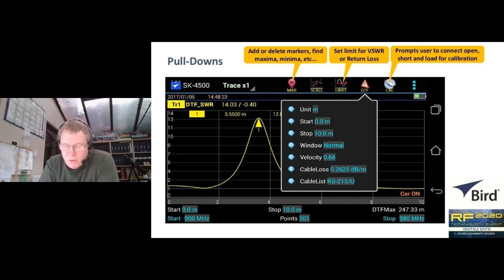This next image shows an example of one of the pull-down menus. This is the menu in which we can specify the type of cable, from which the tester can derive the velocity ratio and hence the speed of propagation through that cable. You'll notice here, at the bottom of that menu, where it says cable list, that we've selected RG213 from that cable list. It's a commonly used coaxial cable for VHF applications. By selecting RG213 from the pull-down, it automatically populates the velocity ratio and the cable loss fields for us. And you can see there, velocity 0.66 or 66%. In other words, that radio wave or electrical wave is traveling along the cable at 66% of the speed of light, about 200,000 kilometers per second.